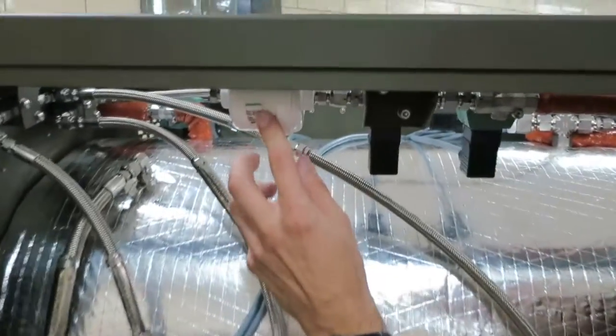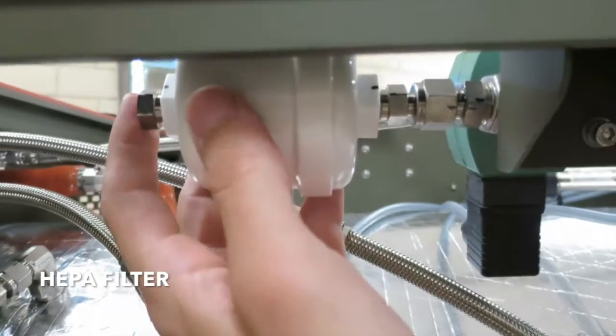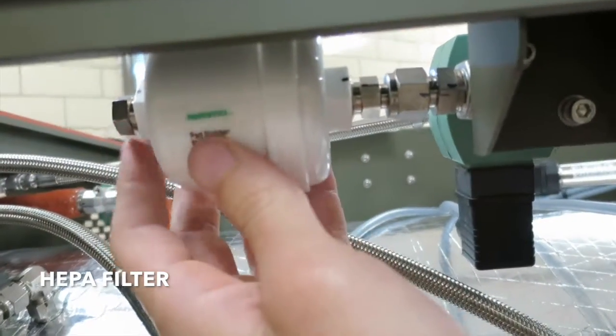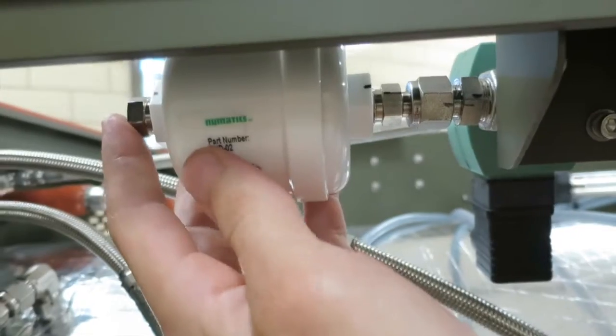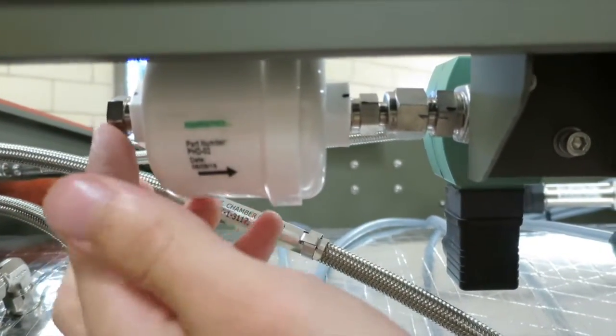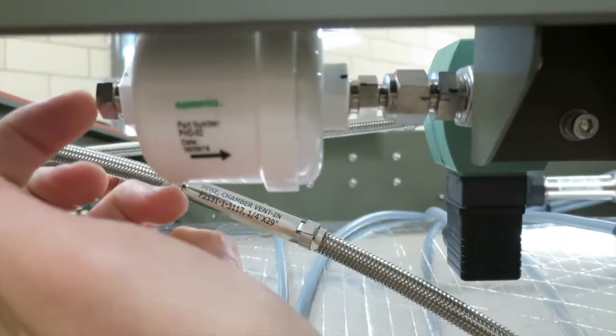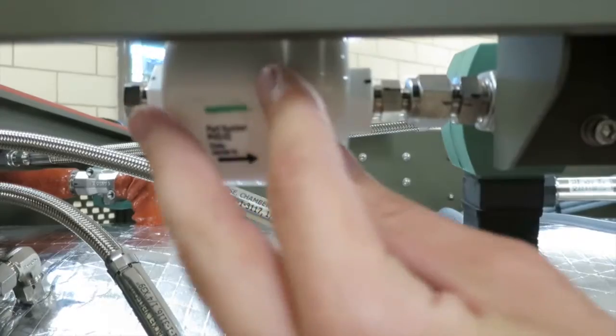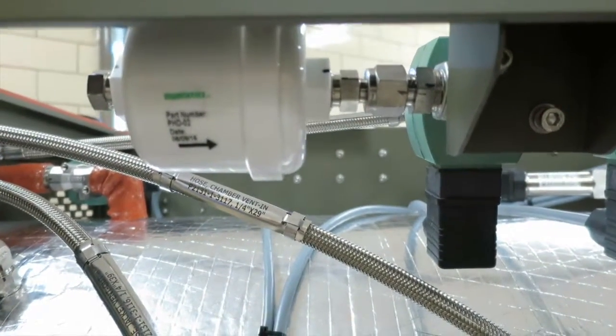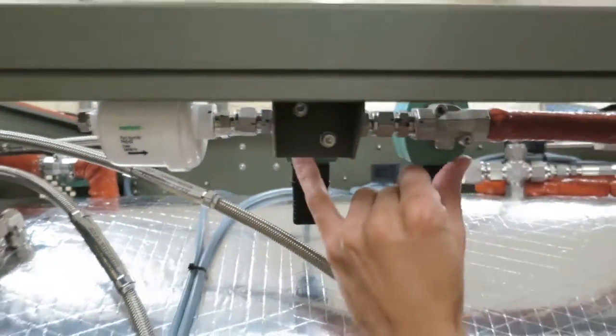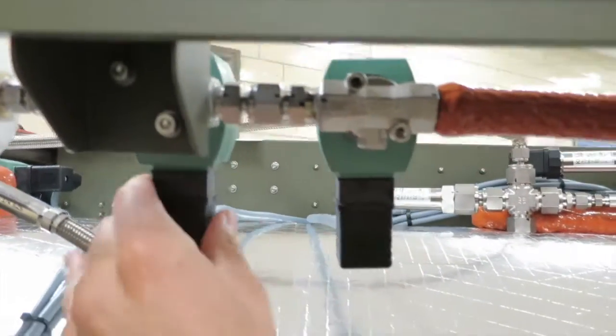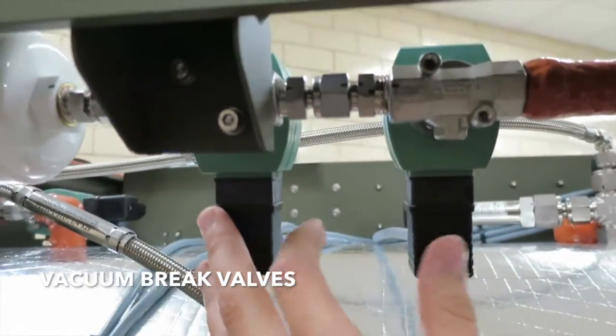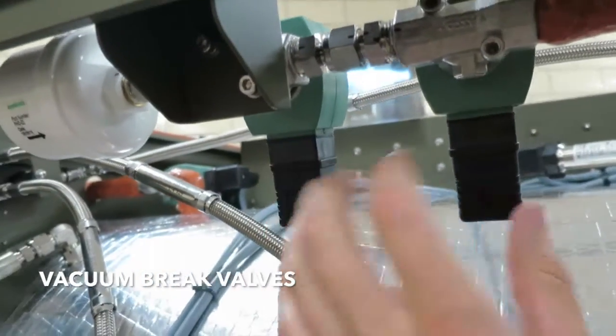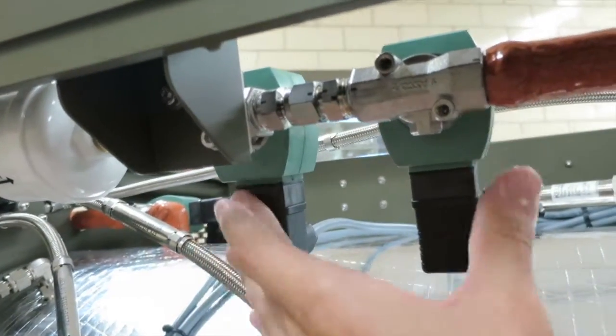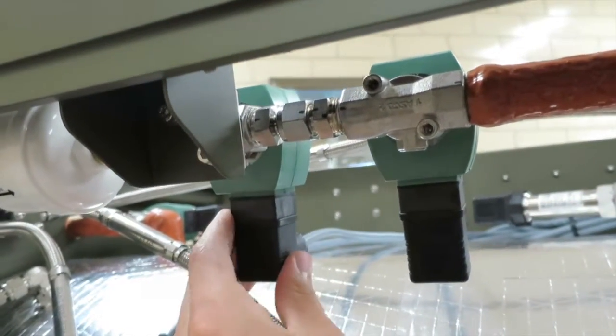So right here we have the HEPA filter. This is to allow, whenever there's a vacuum on the chamber and you want to open the chamber door, you can't allow dirty air to go over the instruments. So air is drawn through the HEPA filter. You know, it's cleaned, all the dirty stuff has gotten out, to break the vacuum on the chamber so you can open the chamber door. These two valves are what open when you need to do that. So whenever you press vent on the PLC, these two valves are activated. Again, they're the same solenoid valves as the vacuum valve.